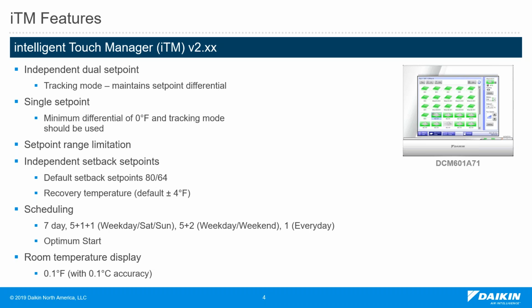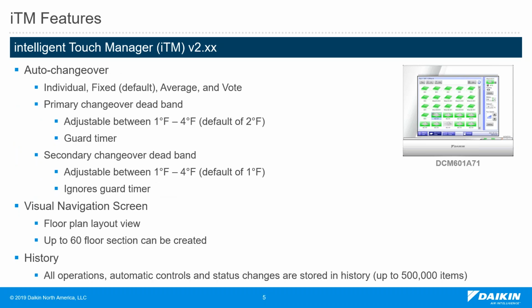Regarding scheduling, we have the 7-day schedule, or 5 days plus Saturday and Sunday, or 5 days plus weekend, or everyday schedule. This is also configurable from the schedule function. Inside the schedule function, we can do optimal start, so we can enable the unit to start earlier than the schedule in order to have comfort at the specific set point. That optimal start is also not available for different competitors. For room temperature display, we can use an accuracy of 0.1 Fahrenheit or 0.1 Celsius as displayed on the iTouch Manager.